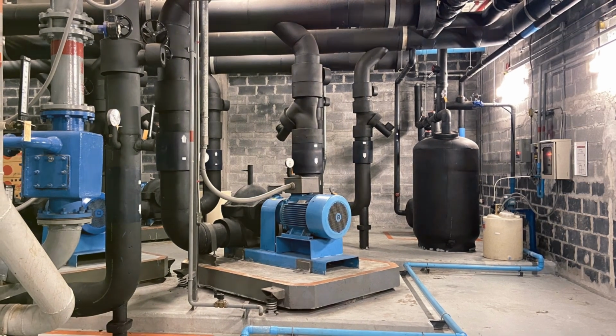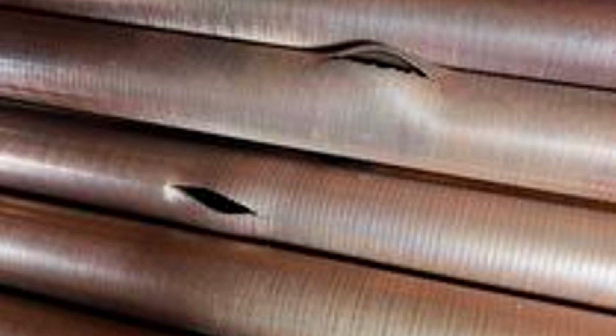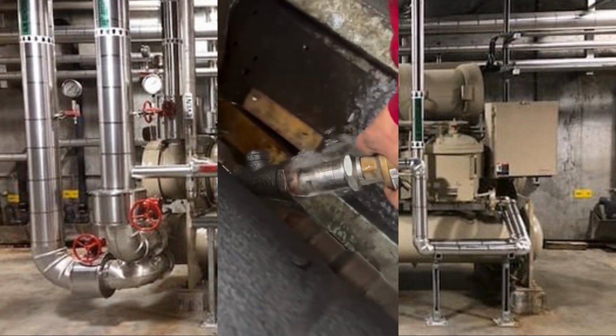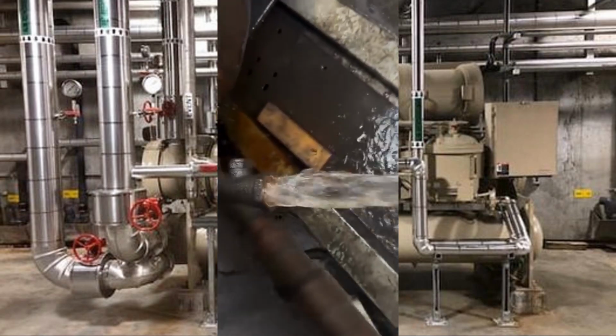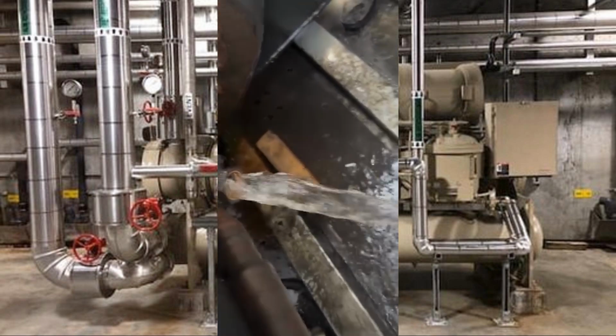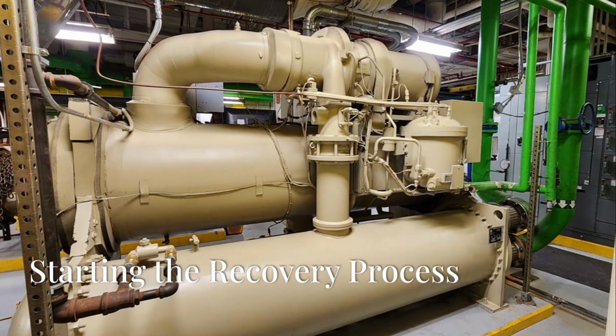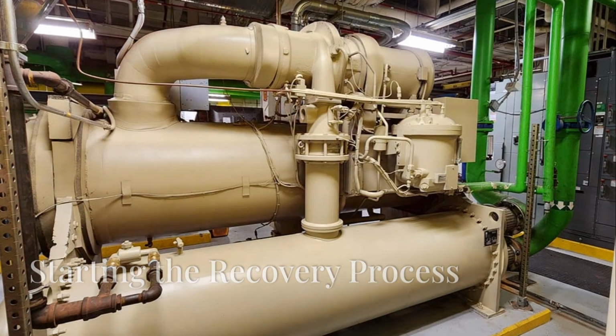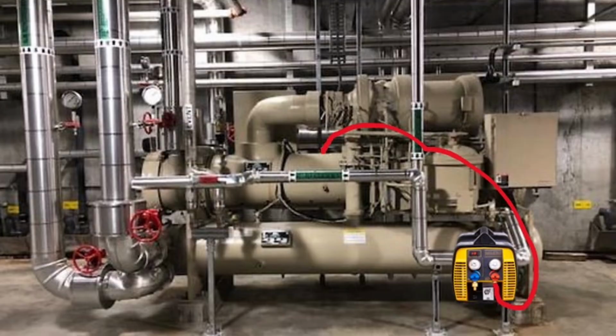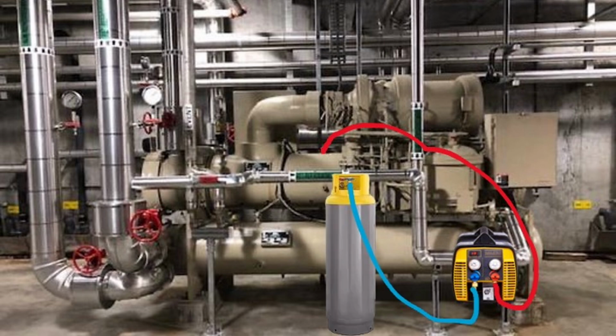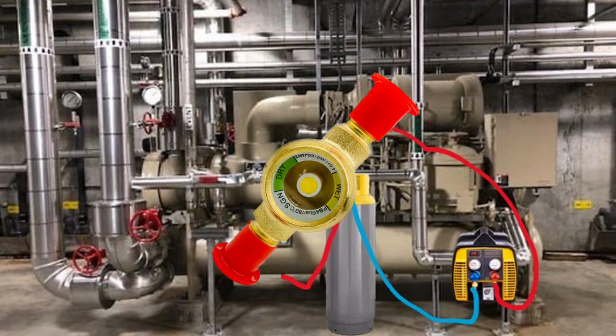If you make a mistake, you will freeze up your machine and flood the system with water, resulting in a substantial amount of downtime and possibly ending your career early because you got injured. In order to set this up, you will connect the discharge of the recovery machine to the top of the evaporator. Then you will connect the suction of the recovery machine to the vapor port on the top of the refrigerant cylinder. After that, you will connect a hose from the bottom of the condenser to the liquid port on the refrigerant cylinder with a liquid sight glass in between.